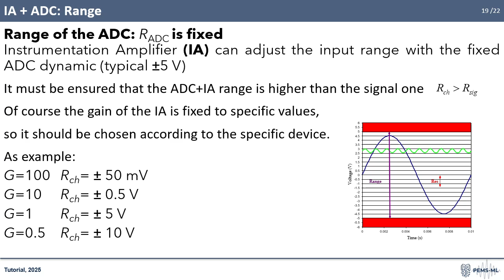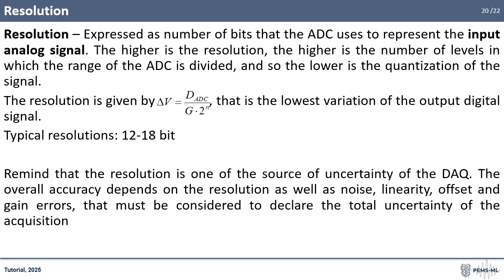In fact, the DAQ is characterized by a specific number of bits of resolution, which, together with the range, defines the quantization error as delta V equal to the range of the channel divided by 2 to the power of n. The lower the range, the higher the resolution. Typical resolutions are of the order of 12 to 18 bits. Given the noise floor of the DAQ, it makes no sense to increase its number, except for highly accurate applications. In fact, it has to be remembered that the total uncertainty of the DAQ itself is not only given by the resolution, but also by the noise of the electronic part, the offset and gain errors, the linearity of the sample and hold, and so forth.